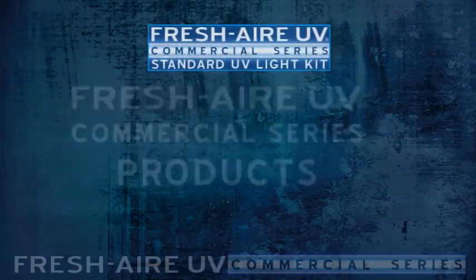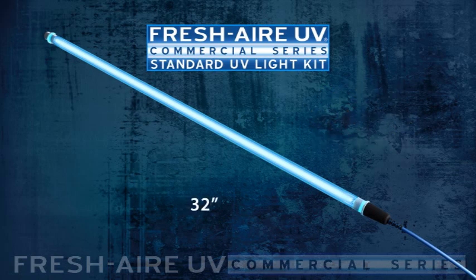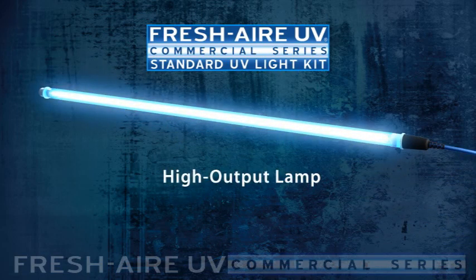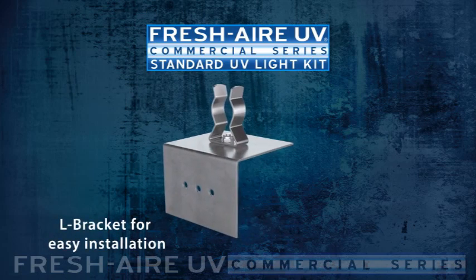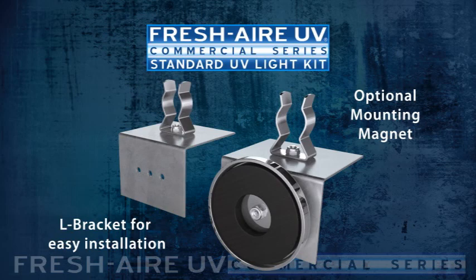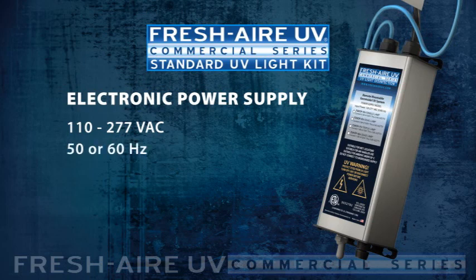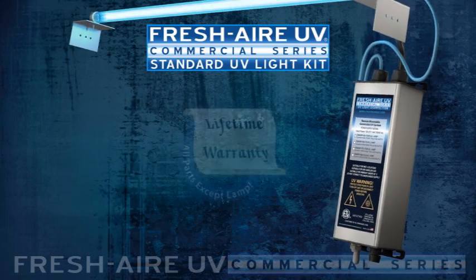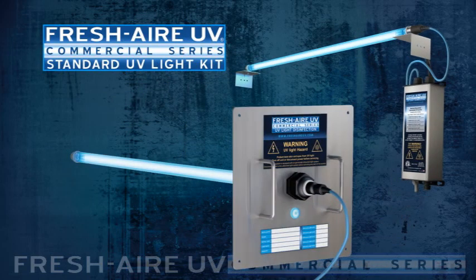Our standard commercial systems feature one or two year Fresh-Aire UV hard quartz UVC lamps, available in 32 or 60 inch lengths. For airborne disinfection applications, 32 inch high-output lamps are recommended. This system comes with L brackets for easy installation. Add optional mounting magnets for even simpler installation onto metal surfaces. The systems are powered by our 110 to 277 volt, 50 or 60 hertz, auto-switching electronic power supply. This heavy-duty ballast comes in a water-resistant NEMA enclosure and has a lifetime unlimited warranty.